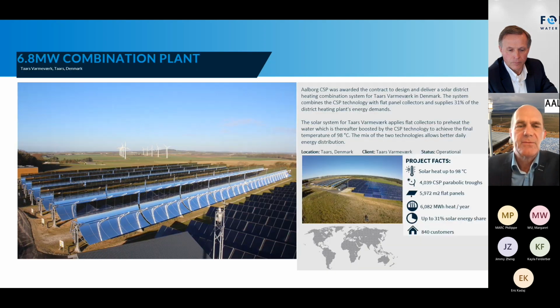On the next slide, here's a combination plant we built, combining a flat panel system and parabolic trough. In the flat panel we preheat the water that is then fed into the parabolic trough system to create higher temperatures. By focusing or defocusing these parabolic troughs, we can modulate the heat output a bit, which makes good sense for operation of the plant.